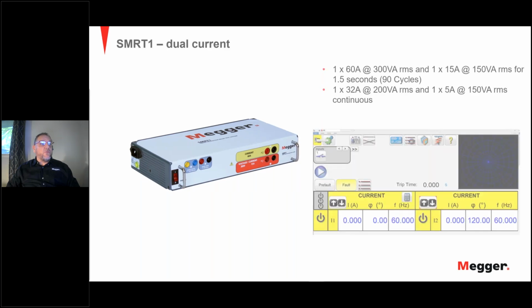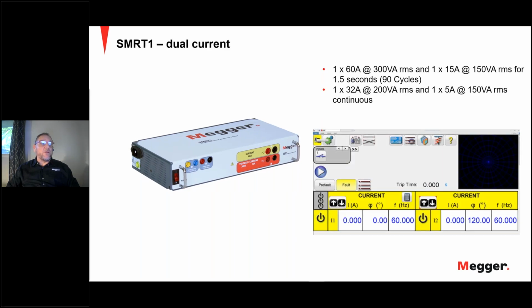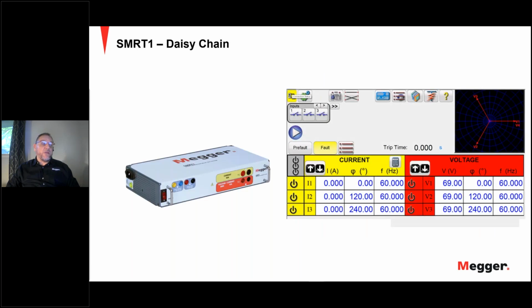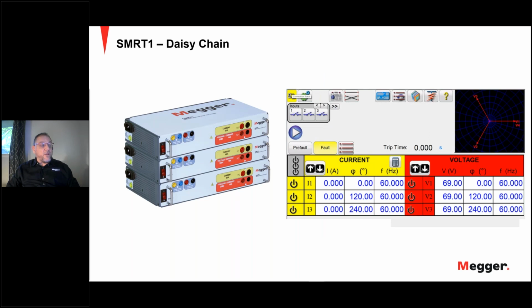So what you can do with the SMRT1 is convert the voltage channel to become a current channel, which will then give you an additional 15 amps at 150 VA for 1.5 seconds, or 5 amps at 150 VA continuous. Just as a note, these features roll over to most of the other SMRTs in the SMRT family. Another excellent feature of not just the SMRT1, but the full range of SMRTs, is that you can daisy chain units together. In this case, you've got 3 SMRT1s daisy chained together to give you a multi-phase system. So you've got 3 currents, 3 voltages, or you can have up to 6 current channels.